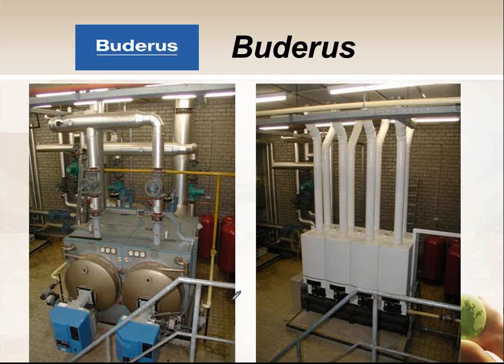in. A boiler plant is best served when it keeps the old same water circulating around it for 20 years, right? We don't want to bring any new water in if we don't have to. Sure, we're going to have a make-up water connection on the boiler plant if we happen to lose water or something like that, but generally speaking, we don't want to bring new water in. We want to keep all the old boiler.